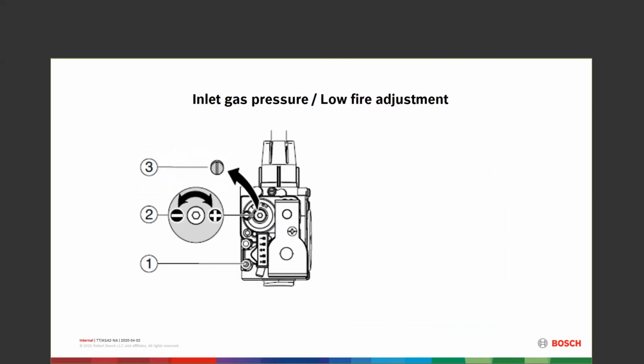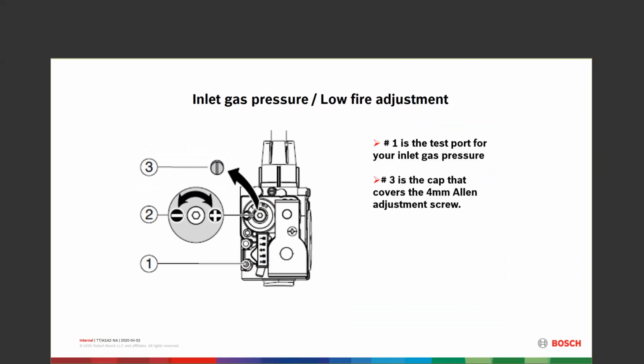Now you're going to do some adjustments on the gas valve. So your low fire adjustment there is actually under the crown. You're going to take off number 3, the little cap. Number 1's the test port for your inlet gas pressure. Number 3 is the cap that comes off, and number 2 is actually a 4mm adjustment screw that's in there for low fire. So you are adjusting gas pressure with that regulator for low fire.